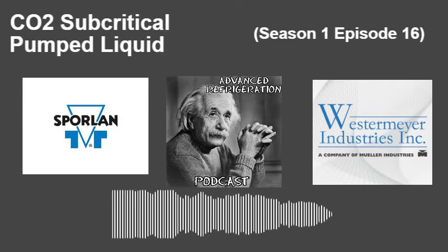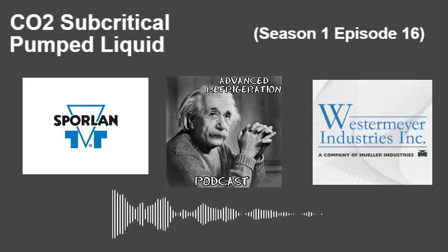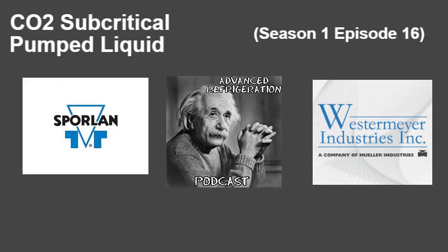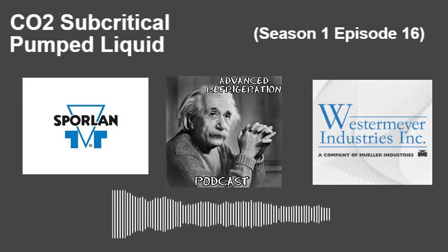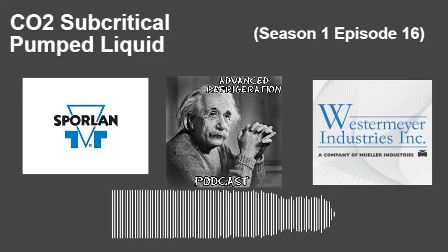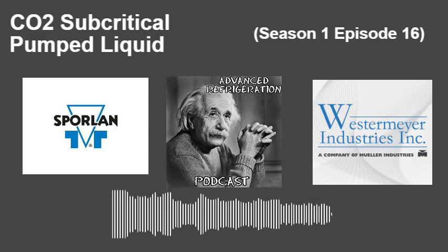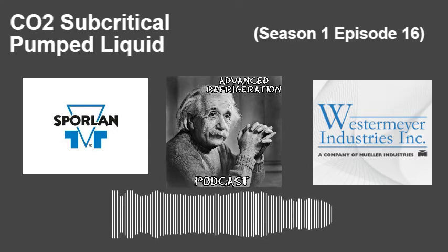So basically, it ensures that it has, like I said, a full column of liquid going down. They use this on screw compressors on Bitzer racks, TurboCool or something like that. Yeah, TurboCool. Basically, they have the same setup where they actually have a horizontal receiver on the drain leg before it actually goes down to make sure for their oil cooling. The reason why is because screw compressors produce so much heat because of the high RPM. So basically, you have to cool it down.